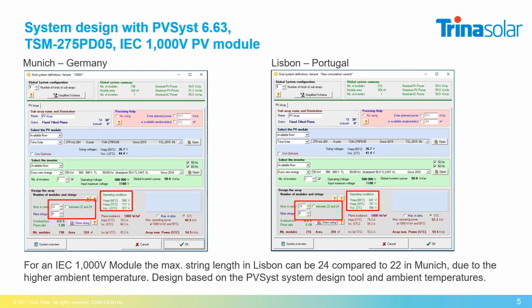Here I'm comparing first what is the impact if I take 1000 volt modules. If I take 1000 volt modules, and if I go to Munich in Germany, you can directly see that the string length, designed with PVSyst, which I used for the whole presentation and whole simulation, is at maximum 22 modules without exceeding the system voltage at the assumed minus 20 degrees, which is approximately 3 degrees higher than the ambient temperature shown before.